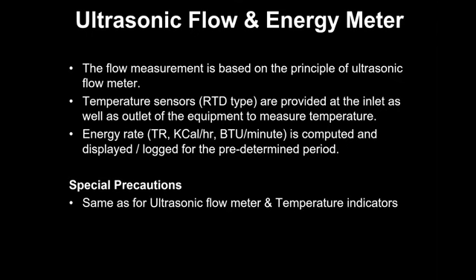Now there are ultrasonic flow and energy meters also. The working principle is the same, there's not much of a difference, but it also has two RTD sensors, which can be at the inlet and outlet of the equipment. So it will measure the temperature. The temperature data will go to the same meter. It already has flow. You key in the density and specific heat of the liquid, and it will calculate TR, kilocalorie, BTU. It will be provided to you.